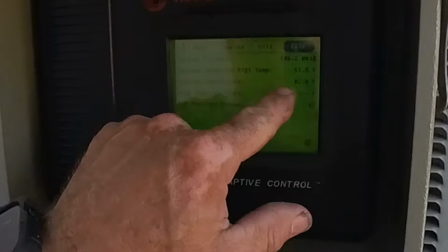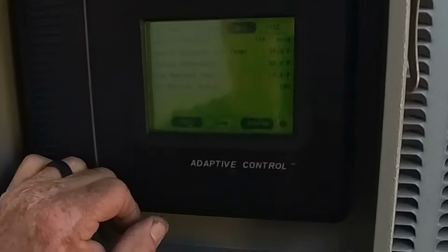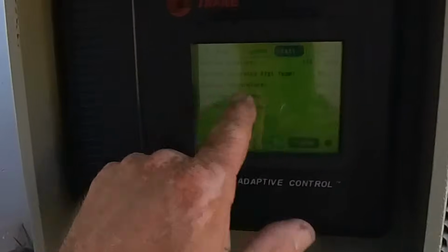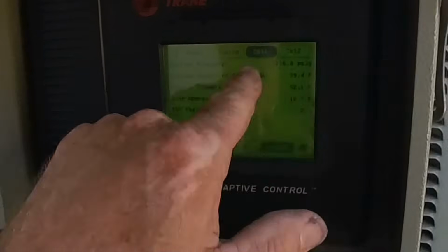Alright, let's go back. Operator, circuit 2. Suction temperature says it is 81. Saturated is 51. Circuit 1 is running. Got 52 suction temp, 39 saturated. So let's pull some covers off and take a look at that sensor.